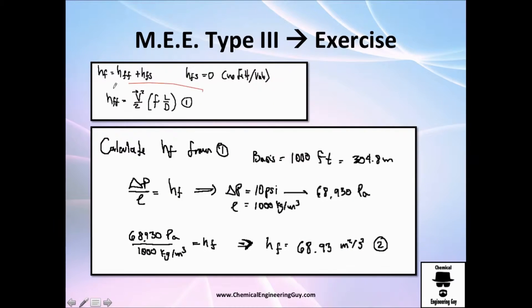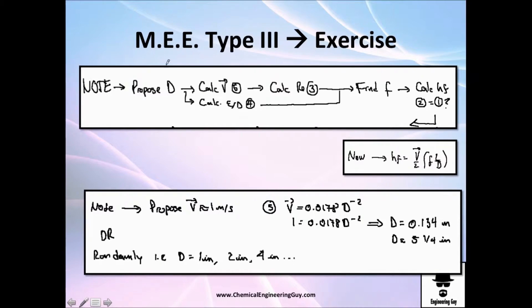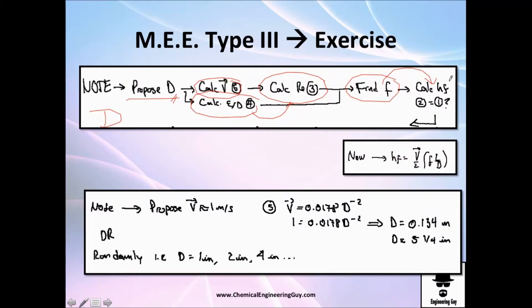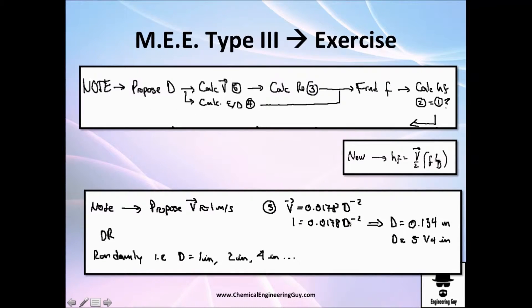We now have equations 1 through 5. To find the diameter, we must propose a diameter, then calculate velocity, relative roughness, Reynolds number, friction factor, and finally friction loss — then compare that calculated friction loss with the actual value of 68.9 J/kg. If the calculated value is close to that number, we're done. A useful trick: normal fluid operation is around 1 meter per second, so find the diameter that gives that velocity — which works out to about 5 and 1/4 inches.